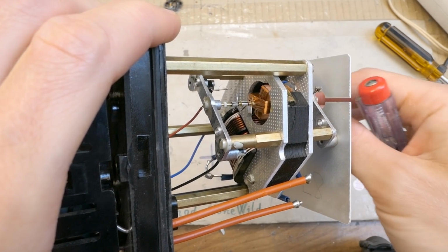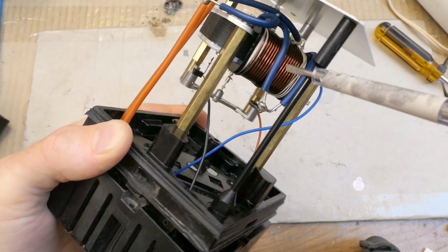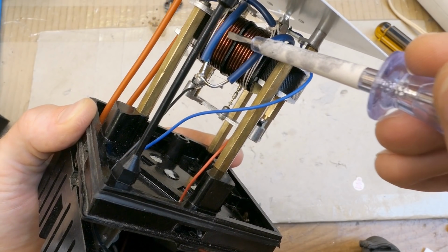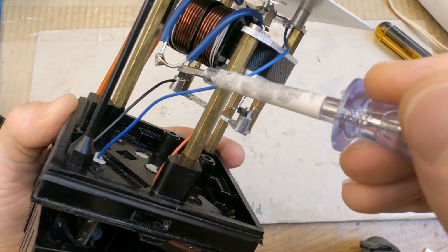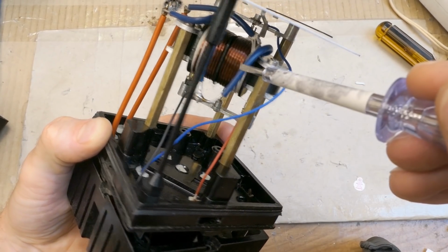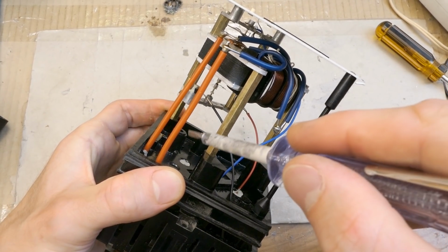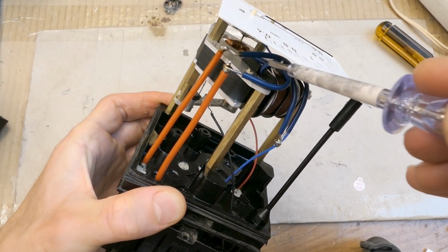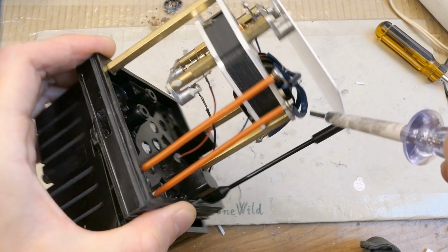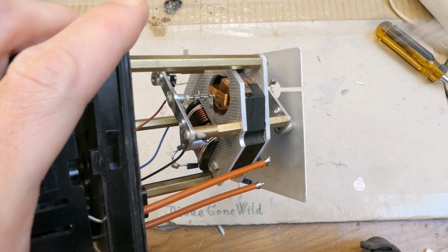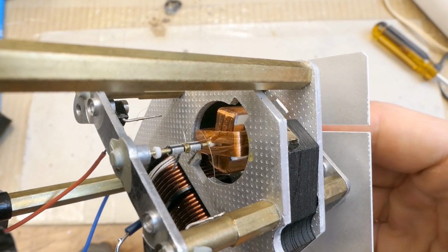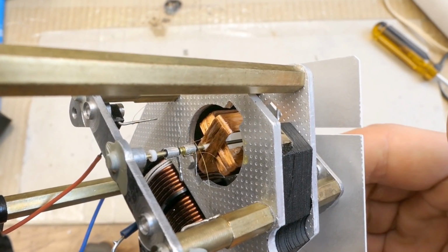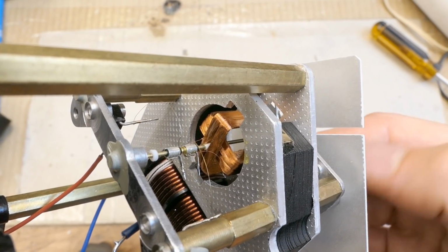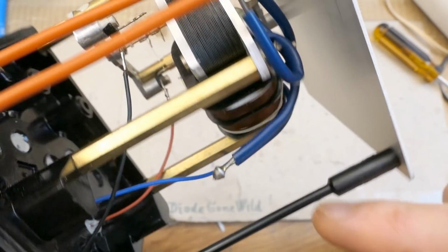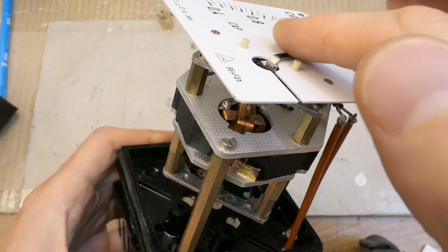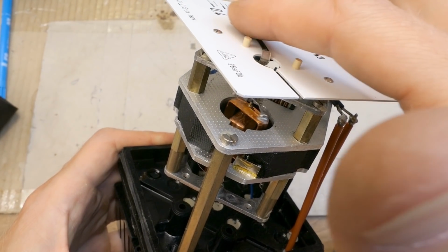And here it is. It's basically this current sensing coil, which seems to be made of 2 sections, but they are just in a series. Here's the connection and the 2 wires going to the current sensing coil from the back. And here are the voltage coils. Basically 2 coils at a different angle with some connection springs or wires, turning in the magnetic field of the current coil. And this system is turning the needle.